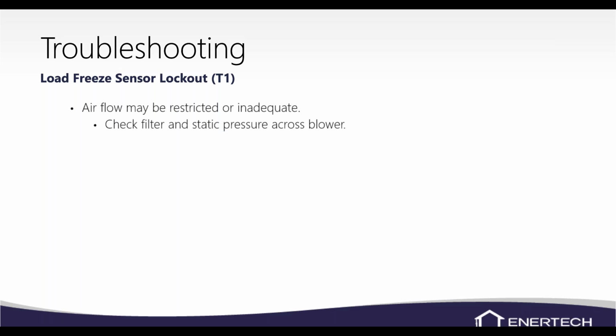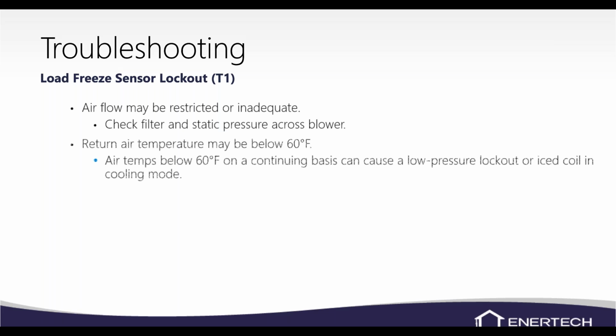If you have a load freeze sensor lockout, that's a T1 sensor, and if you've got a water to air unit, it's looking at your air coil. So your airflow could be restricted or inadequate. Make sure your blower is changing speeds, or make sure it's spinning in general. Check your filter and your static pressure across your air coil there.